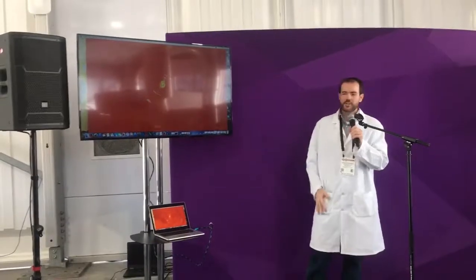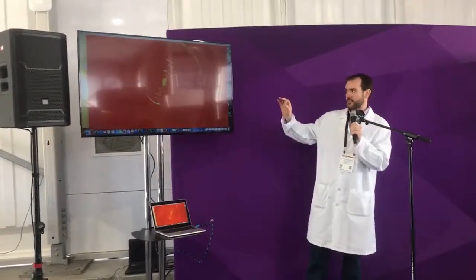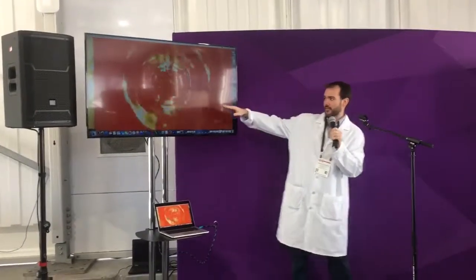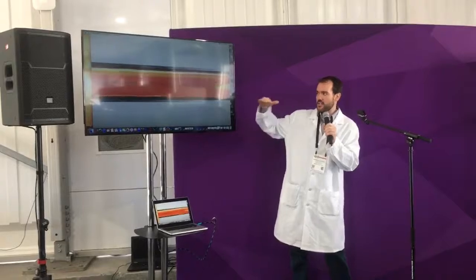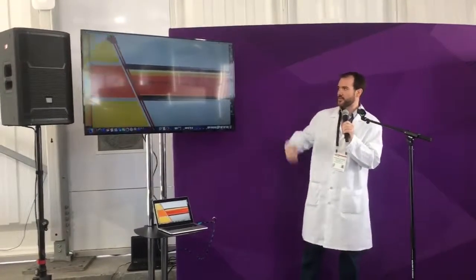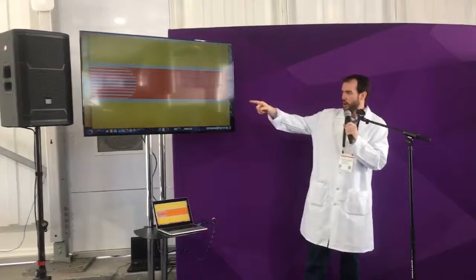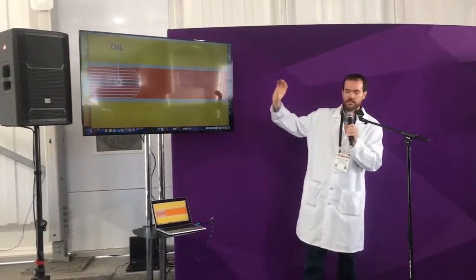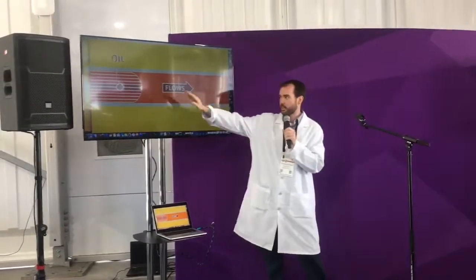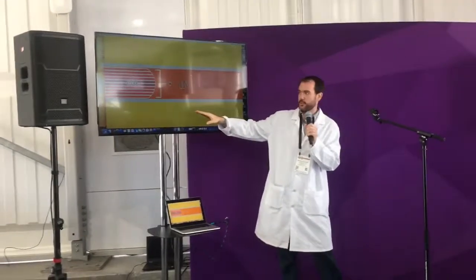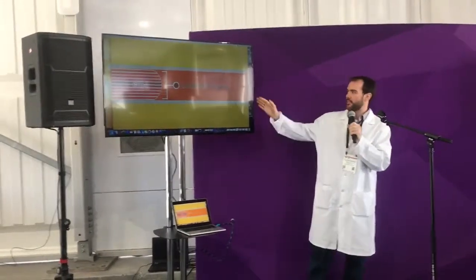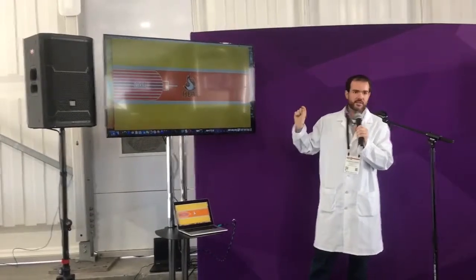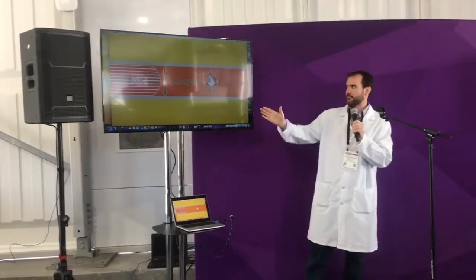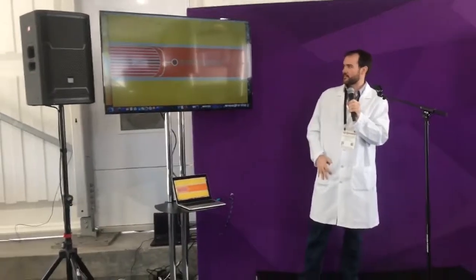So moving along into the oil stream, into the heat exchanger, we'll show you some of the fundamentals of the internal features first: the offset strip fins that are used to help the oil flow. You can see them here. As the oil flows through the passages, there are a series of fins that are offset from each other as you go. That takes your large oil flow boundary layer, which is not good for heat transfer, as heat has to move from the center all the way to the walls of your tubes, and instead you're able to break up these laminar layers into smaller layers that allow faster heat transfer. As we advance on, you'll see what it looks like.